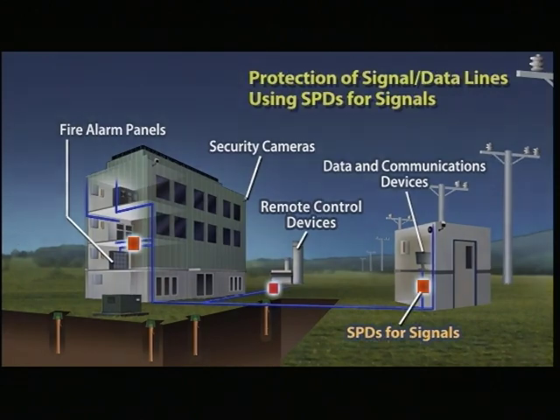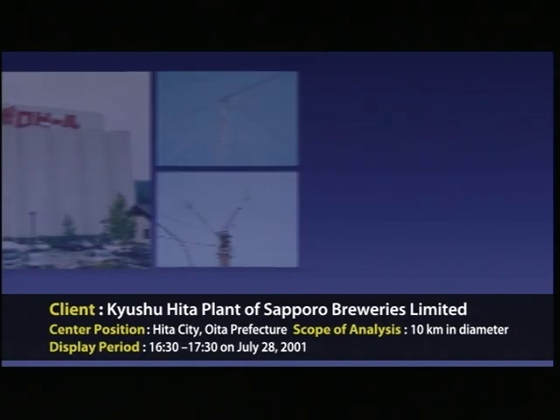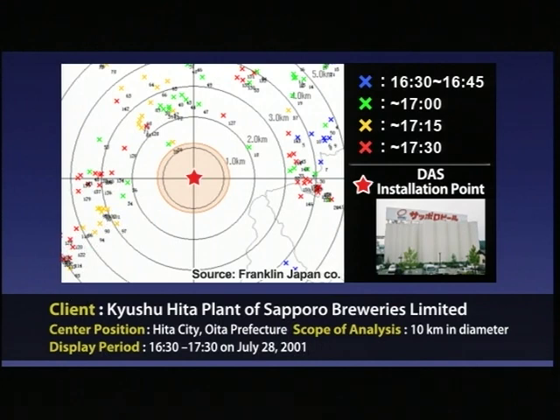Now let me introduce data showing the proven success of the DAS lightning protection effect. This DAS installation point is a plant of a leading Japanese beverage manufacturer. This chart of lightning strike analysis data plots the spots of lightning strikes in a time series over one hour from 4:30 p.m. to 5:30 p.m. on a day when large-scale thunderclouds appeared above the plant. Despite the many lightning strikes that occurred in the vicinity, no lightning was recorded within a 1.3 kilometer radius of the DAS installation point at the center of the chart. In fact, the plant had been seriously damaged by shutdown of production lines due to lightning strikes almost every year before the DAS was installed. Since its implementation in 2001, however, there has been no lightning damage reported.